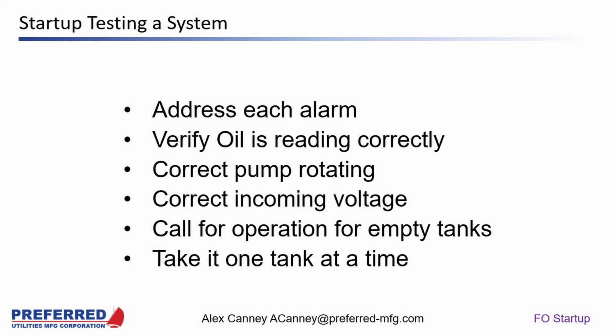Then you start with whatever it might be, whether it be a boiler loop, and you have to initiate a call for operation and verify. But before you can do that, you need to make sure the pumps are rotating correctly, verify the voltage coming in matches the data plate on the motors, verify that the amperage is correct and you're not overamping, and that the overloads are set properly. These are initial steps you need to take before you actually start pushing fuel out.